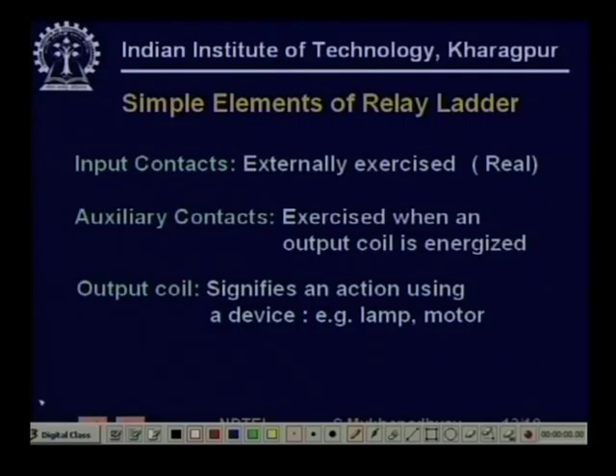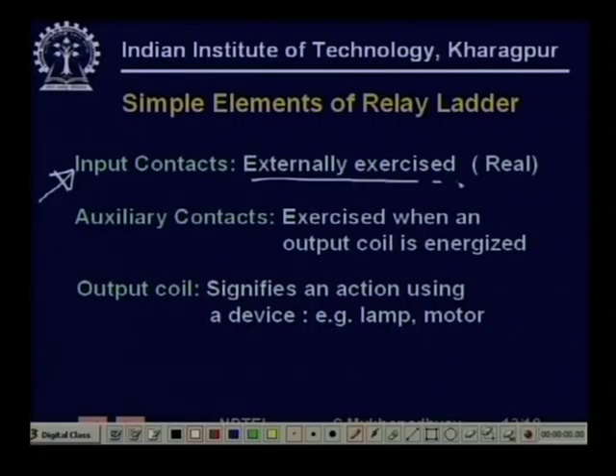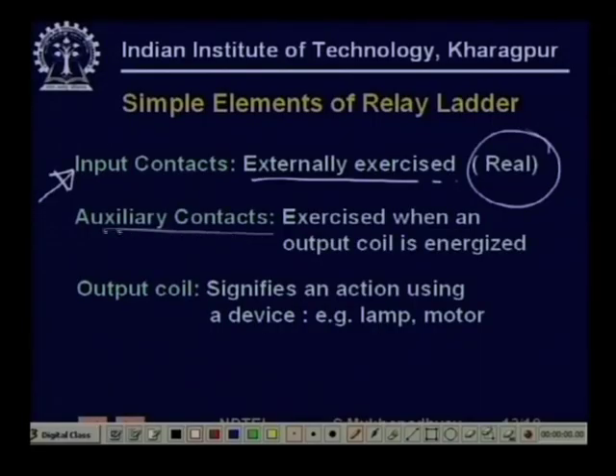The switches are of two types. Some are called input contacts, which correspond to real physical inputs — for example, a photo detector detecting a part and going to 1, a limit switch, a pressure switch, or a push button pressed by the operator. Such contacts are called input contacts, exercised externally by the machine, meaning external to the PLC, and corresponding to real physical devices.